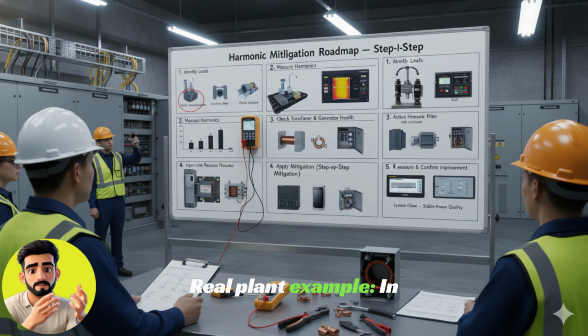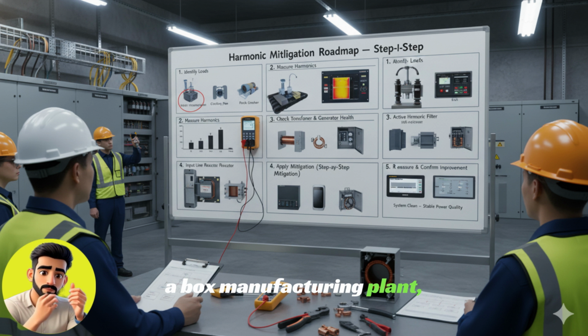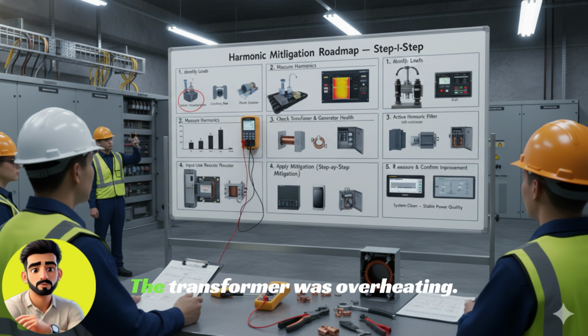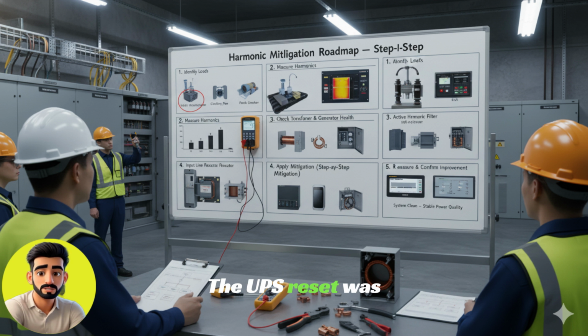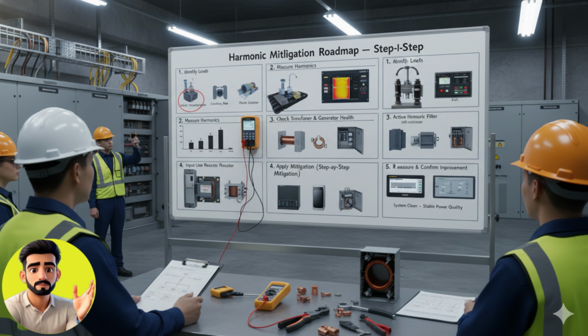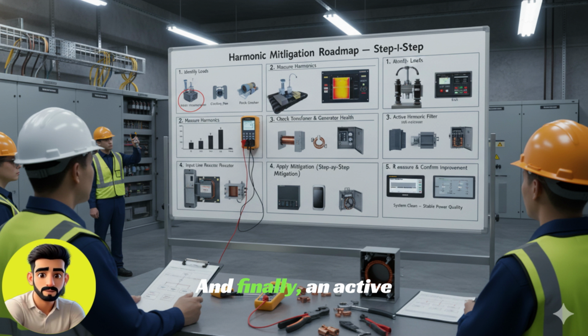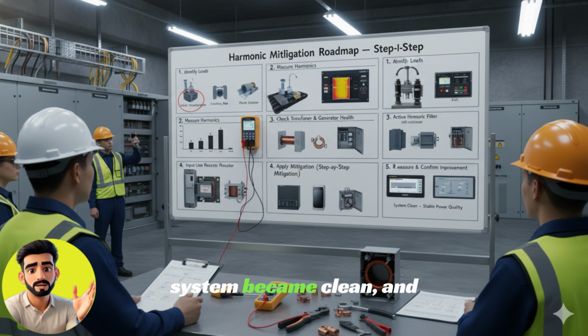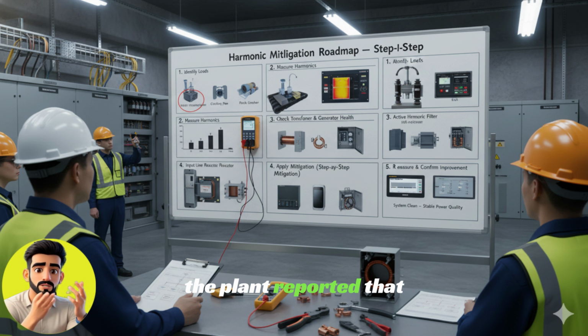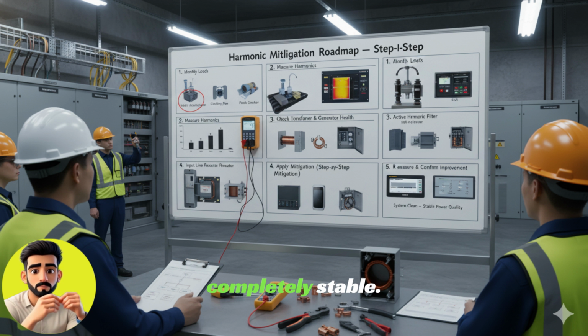Real plant example. In a box manufacturing plant, multiple drives were installed. The transformer was overheating. The UPS reset was done, and digital sensors gave incorrect readings. A step-by-step strategy was followed. A line reactor was installed. A DC choke was installed. A passive filter was tuned. And finally, an active filter was used. In 3 weeks, the system became clean, and the plant reported that power quality is now completely stable.